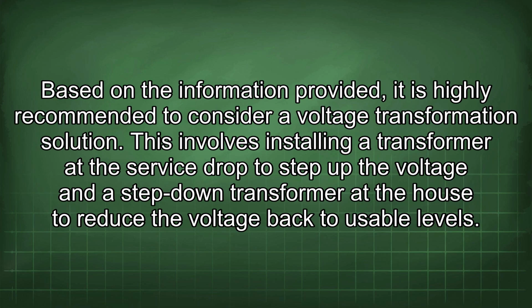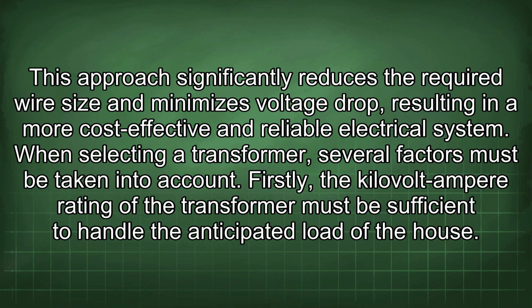Based on the information provided, it is highly recommended to consider a voltage transformation solution. This involves installing a transformer at the service drop to step up the voltage and a step-down transformer at the house to reduce the voltage back to usable levels. This approach significantly reduces the required wire size and minimizes voltage drop, resulting in a more cost-effective and reliable electrical system. When selecting a transformer, several factors must be taken into account.